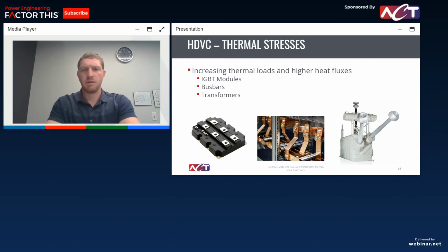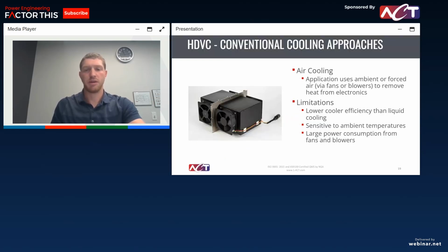As Knut alluded to here, one of the main challenges that we're seeing with HVDC and a lot of power electronics right now is increased thermal loads and higher heat fluxes. A lot of components like IGBTs, thyristors, high capacity bus bars, transformers, we're seeing higher and higher heat fluxes, and conventional cooling solutions such as air-cooled or single-phase pumped loops are not up to the challenge of cooling those.